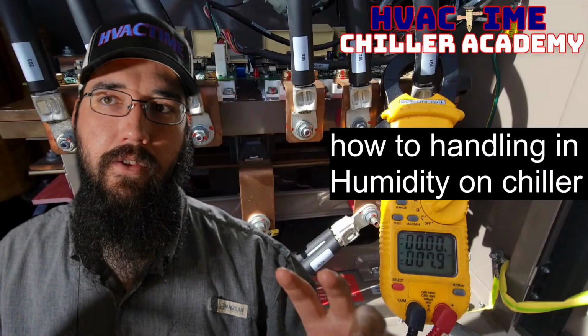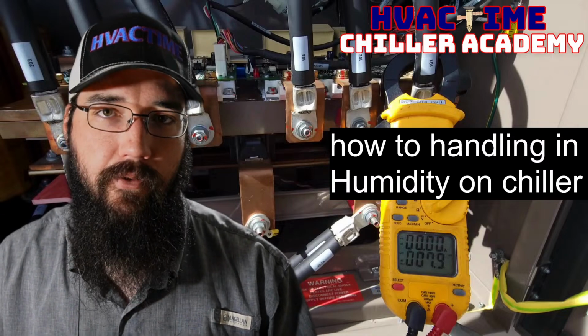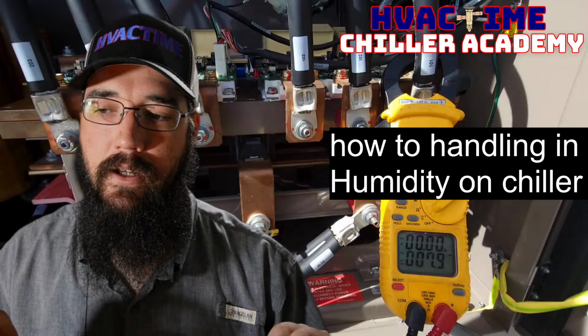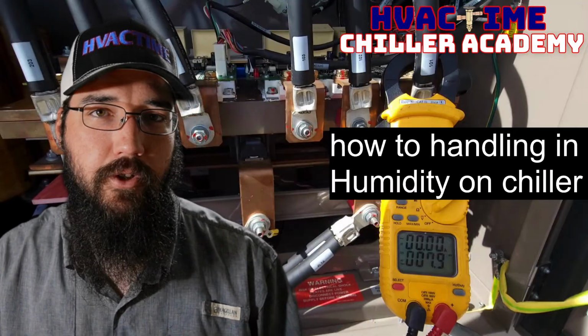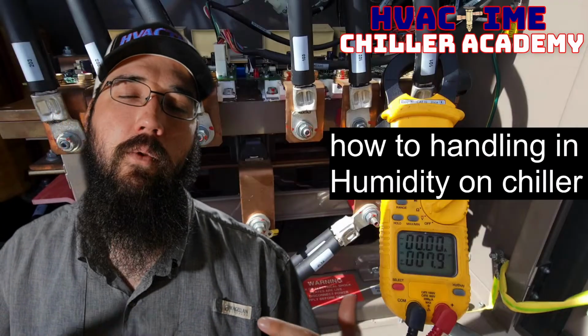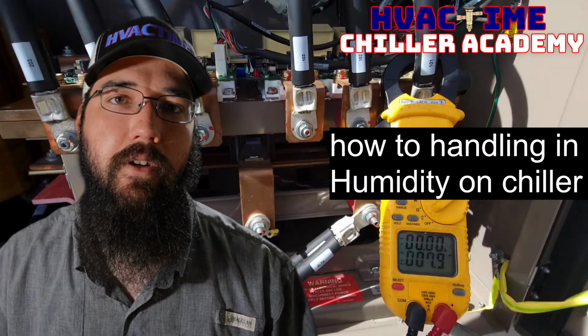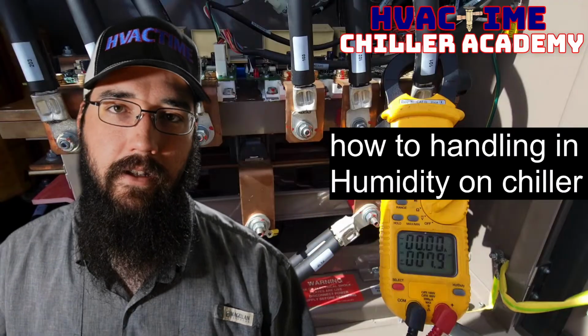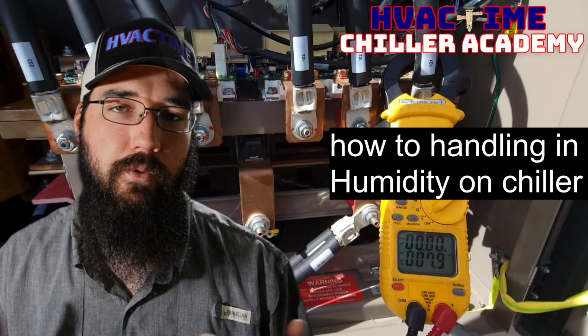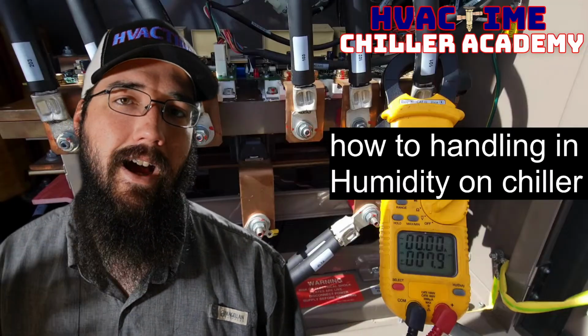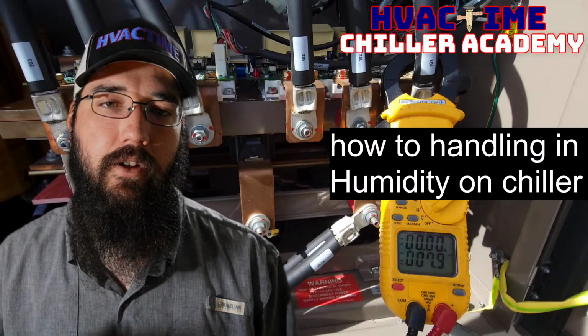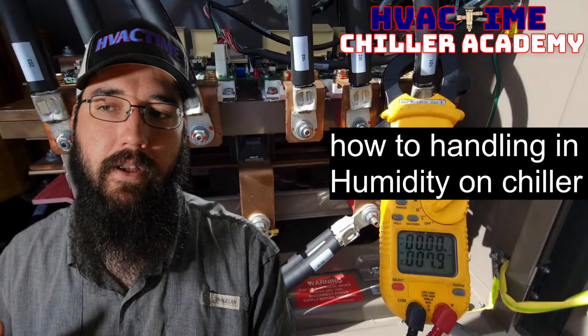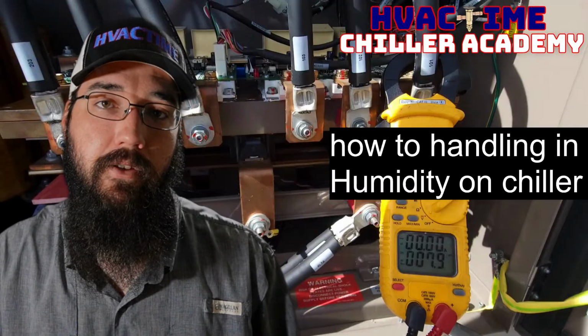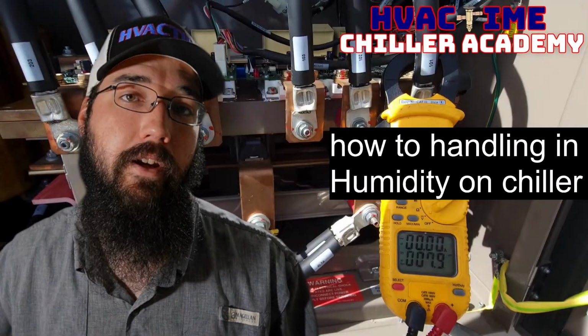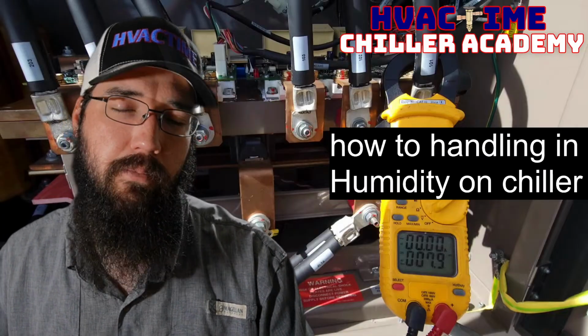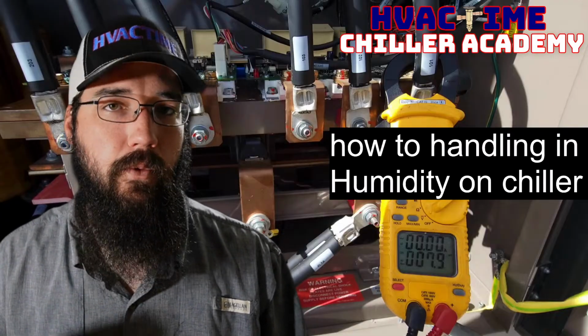clarify with this is, think of why we try to go for 45 degrees for comfort cooling, as an example, for chill water. Why do we shoot for those mid 40 temperatures to begin with? Well, it comes back to trying to achieve dehumidification, right? Technically, if all we were worried about was sensible load, and we just need to achieve a certain air temperature, we could run higher chill water temperatures and achieve a temperature set point. We can hit 70 degrees with higher chill water temperatures than the mid 40s. And we could probably be far more energy efficient, because all we're doing is hitting the sensible set point, if we're not taking latent heat or humidity into account.